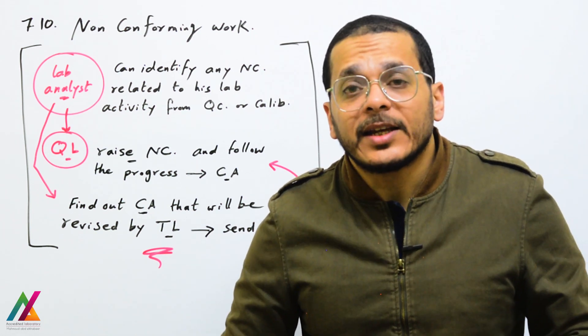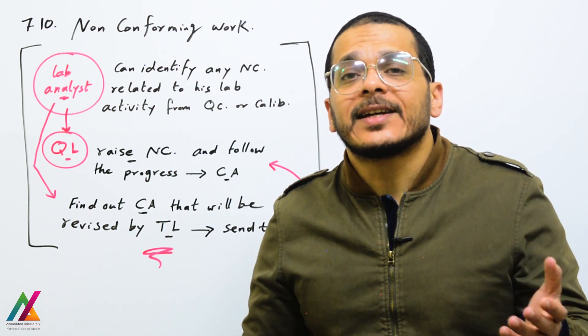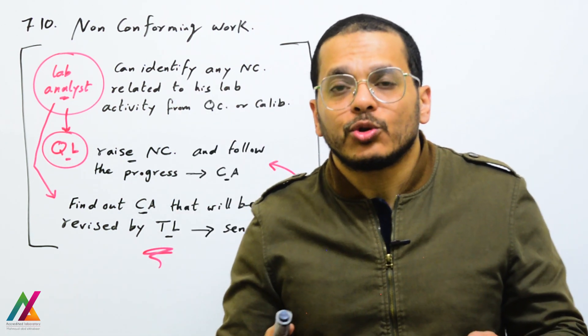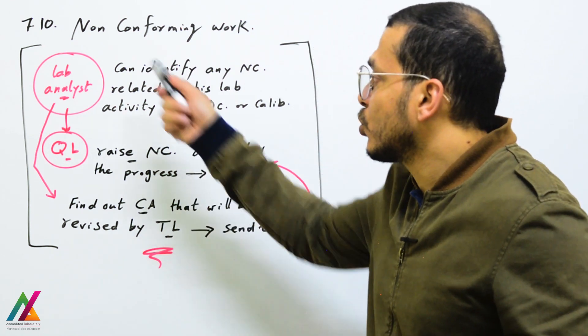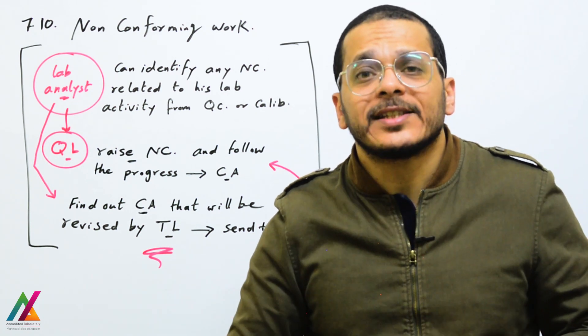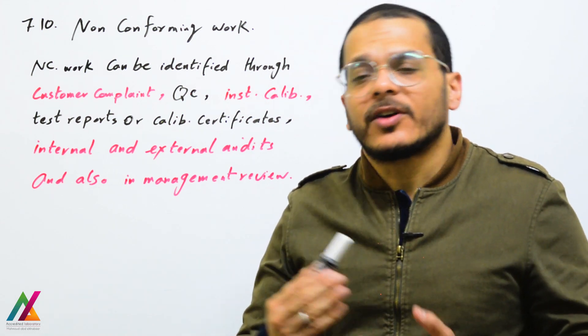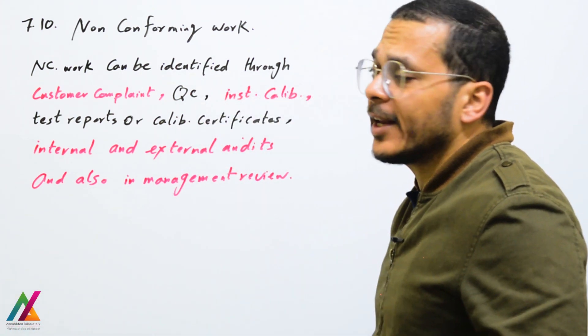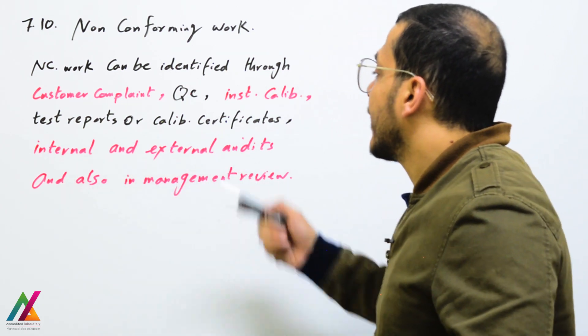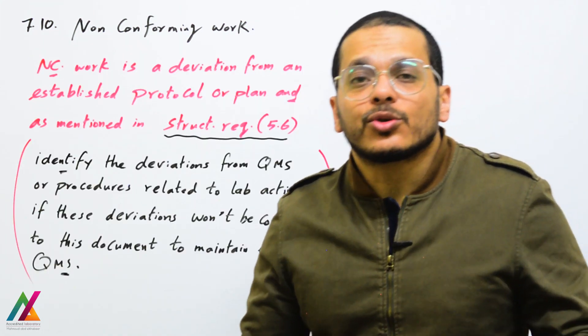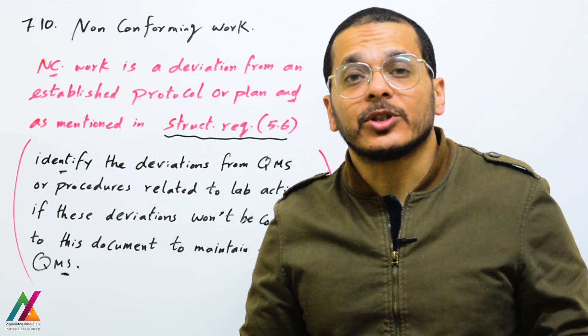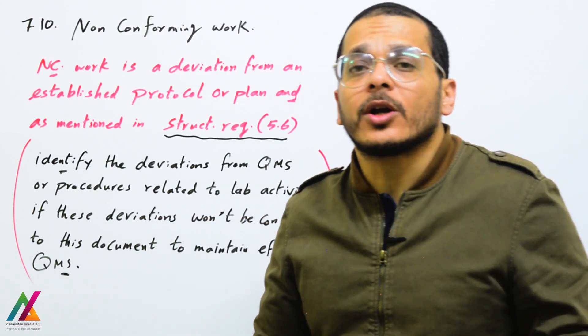Non-conformity can also be raised during an internal audit by the quality lead or during an external audit by the accreditation body. In both cases, the same process shall be followed. Non-conforming work can be identified through customer complaints, quality control results, calibration, instrument calibration, test reports or calibration certificates, internal and external audits, and also during annual management review.